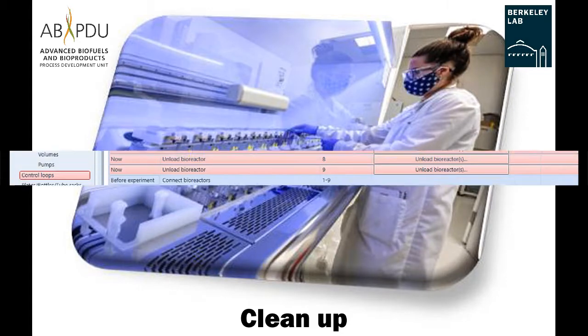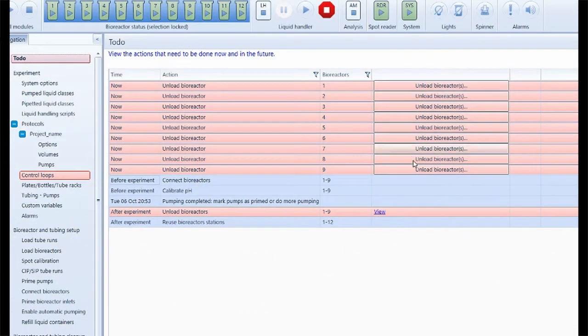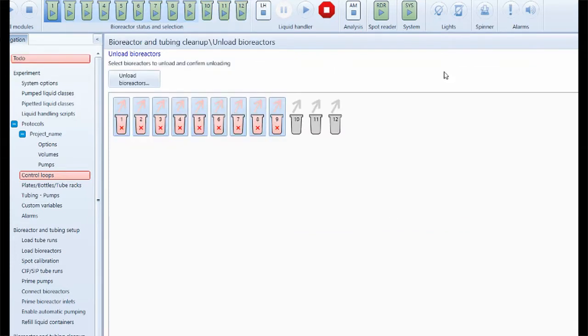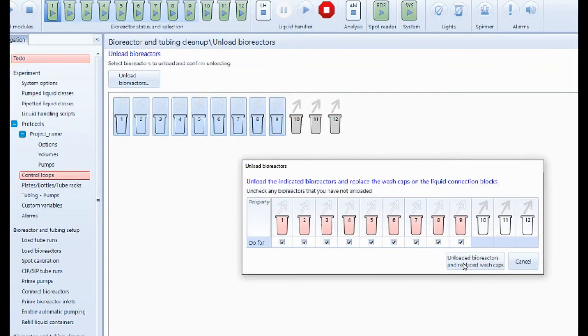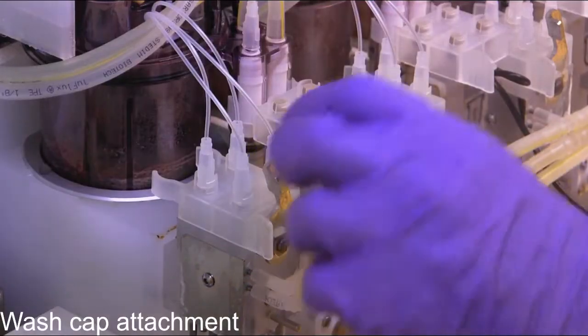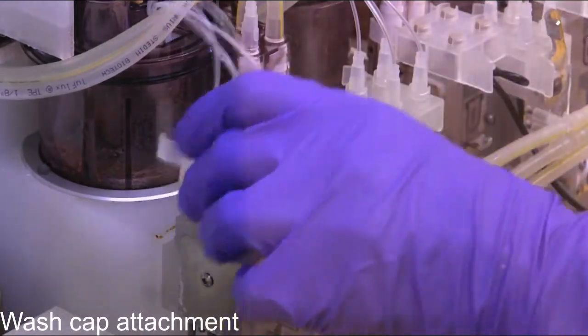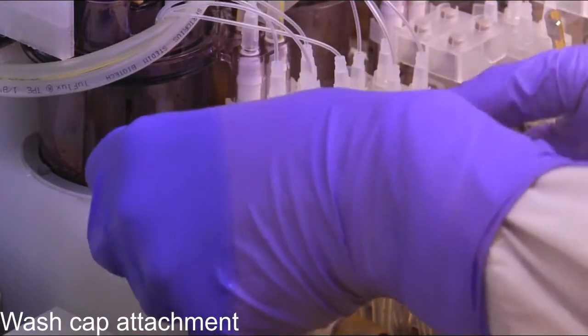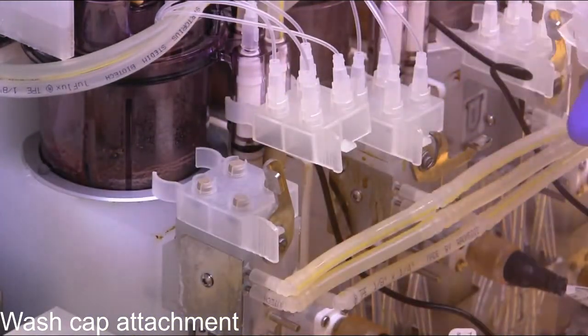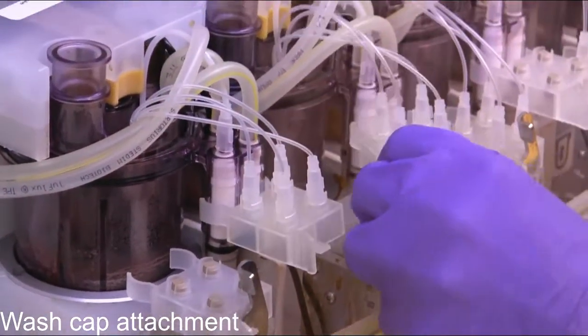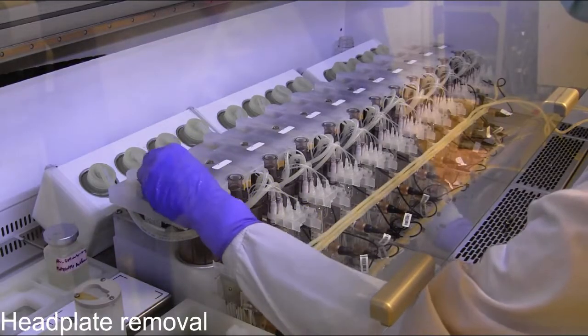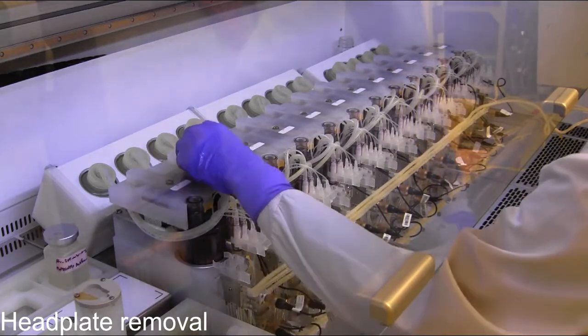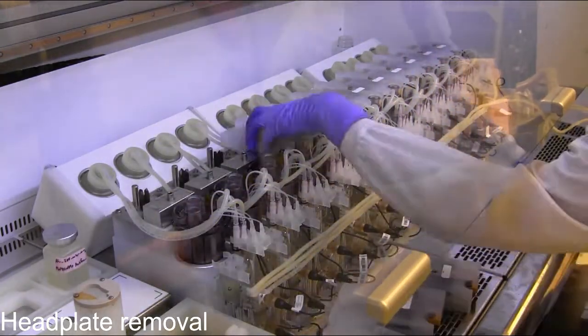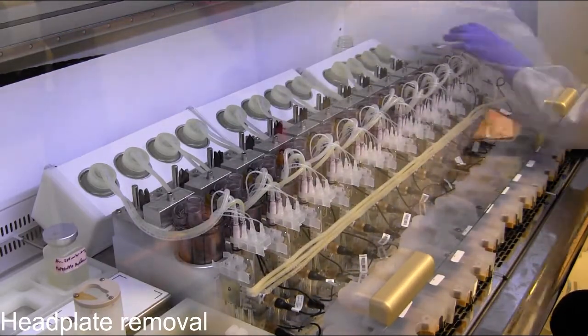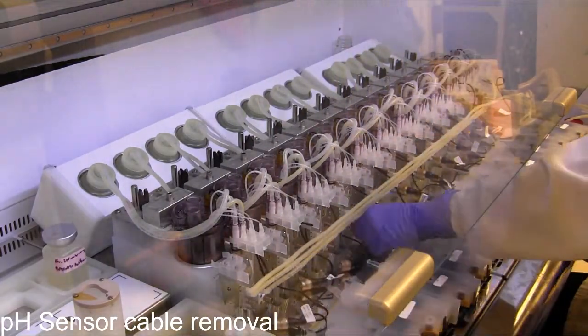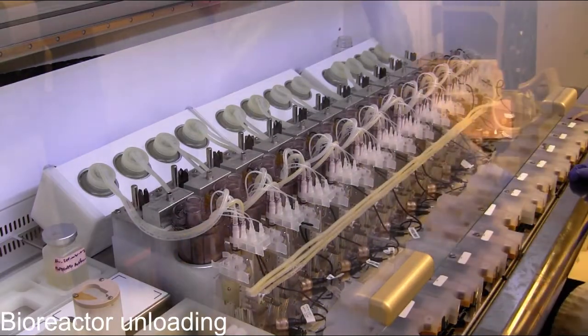Cleanup. Once the experiment is complete, the next stage is to clean up. Cleanup is relatively straightforward. The bioreactors are being taken down in reverse order as they were set up. So to start, replace the manifold with the wash caps. Remove the head plates. Disconnect the pH sensor cables and take out the bioreactors.